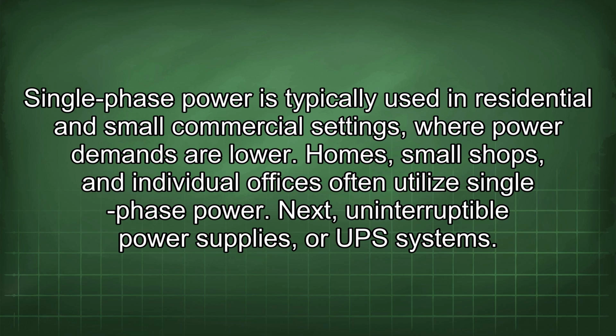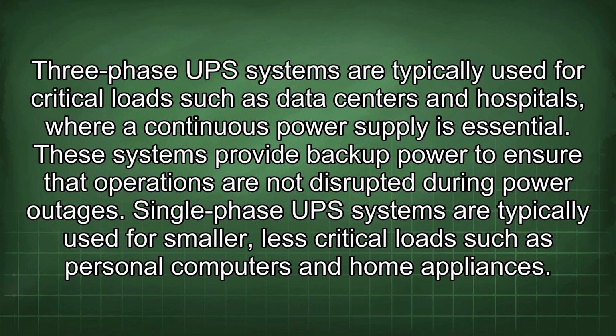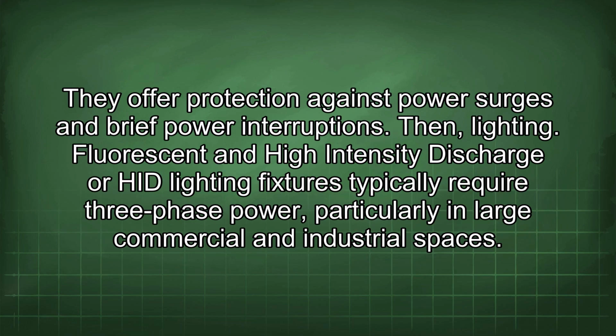Next, uninterruptible power supplies, or UPS systems. Three-phase UPS systems are typically used for critical loads such as data centers and hospitals, where a continuous power supply is essential. These systems provide backup power to ensure that operations are not disrupted during power outages. Single-phase UPS systems are typically used for smaller, less critical loads such as personal computers and home appliances. They offer protection against power surges and brief power interruptions.